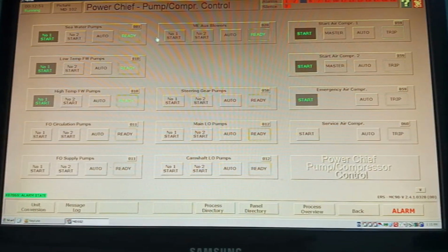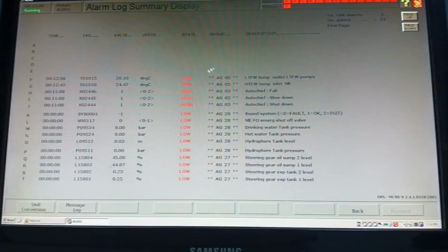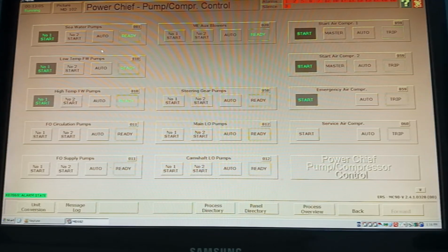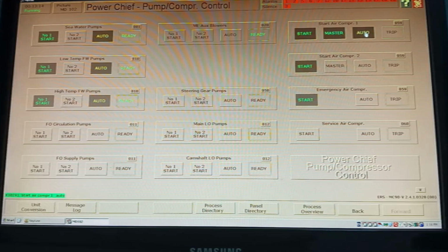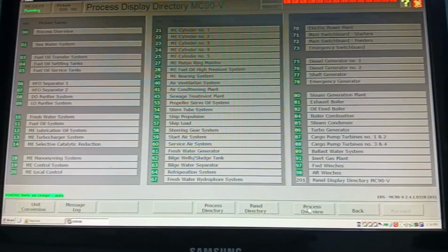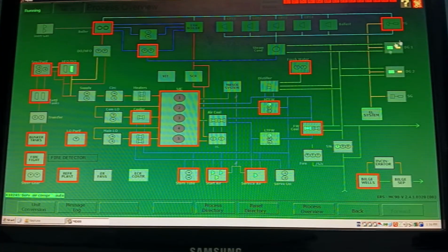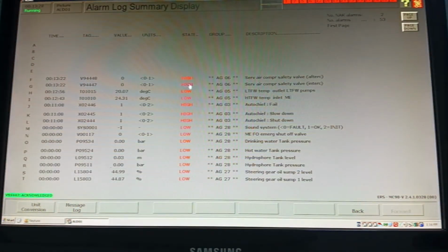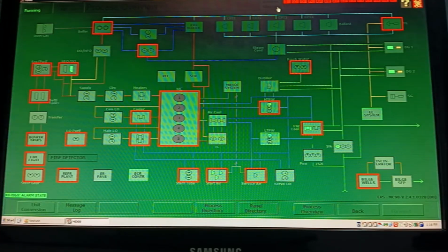Now go to your panel directory. This is your power chief. So here you set your systems to auto. So whichever pumps you set as remote, those will be automatically turned on or turned off when you give auto here. Set any one compressor on master and turn on auto. So when you come to your process overview, you can see your DG1 and 2 running. So that's the main goal of this exercise.